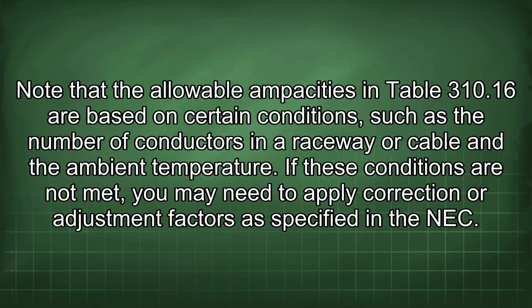Note that the allowable ampacities in Table 310.16 are based on certain conditions, such as the number of conductors in a raceway or cable and the ambient temperature. If these conditions are not met, you may need to apply correction or adjustment factors as specified in the NEC.